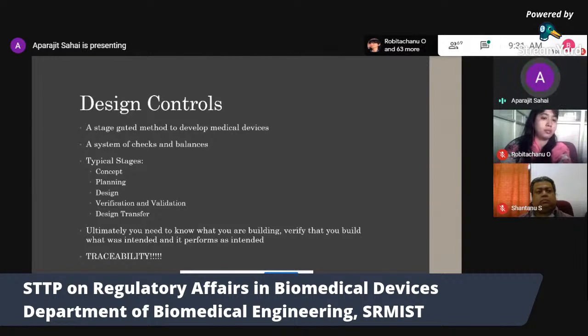I think someone just posted about IEC 62366. Yes, that is the standard for usability. You need to meet that standard. There's also a home use standard, which is 60601-1-11, a collateral standard to 60601-1. In that, there is a specific section that talks about usability.